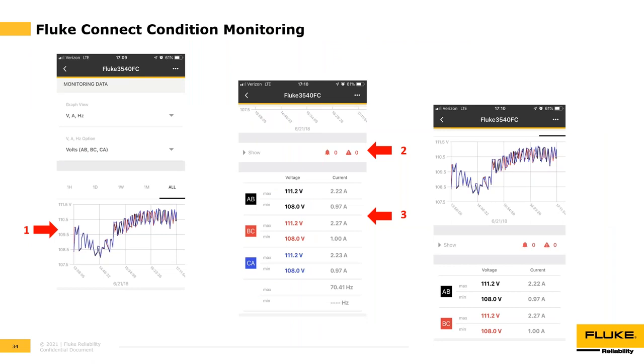So here are some of the screenshots of what remote condition monitoring graphs would look like from the mobile app. These happen to be from our 3540 power monitor. You can see here we've got a graph view of the data next to the number one. Next to the number two, we've got alarms and alerts. Now the difference is that you set up the alarms, so you can say, hey, if my voltage goes over 112, I want to be notified. That's an alarm. And then you've got system generated alerts, such as, oh no, the 3540 has lost power.